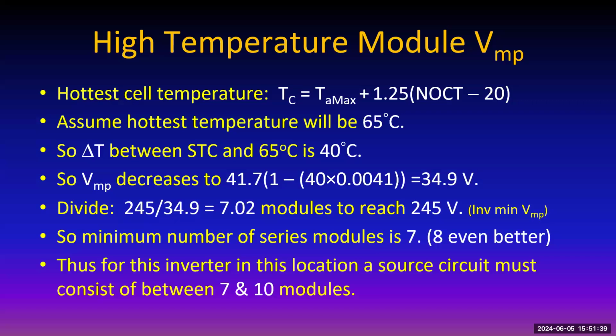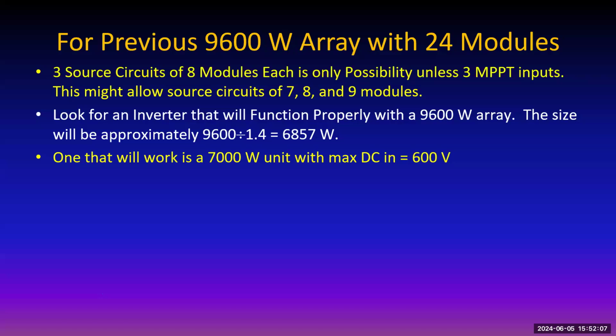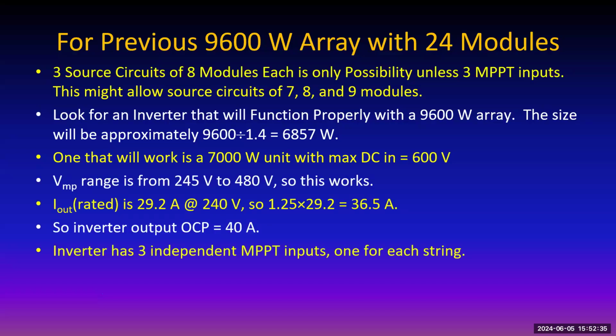That's a lot different from what we're looking at in these other circuits. So this is something you need to think about if you want to get rid of the cost of either the optimizers or the microinverters: can you lay your system out with strings between 7 and 10? And if you're between 7 and 10, let's see what it does to the circuit we're trying to do here. It turns out with 24 modules, we have to do 3 times 8. We could do one with 7, one with 8, and one with 9, but to do that, we'd have to have 3 maximum power point tracking inputs. We may or may not be able to have that. It depends on the inverter. So anyway, let's do it the simple way with 3 of 8 and see what that does for us. And what's that going to look like?